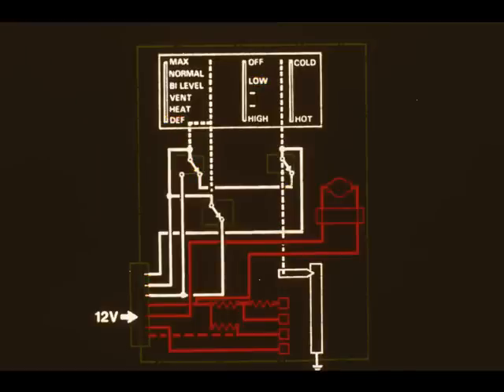The blower motor and speed control can each be tested using a 12-volt supply. Connect it to pin 5 of the 7-way socket. The motor speed should increase as successive selections are made. The highest fan speed can only be obtained by earthing terminal 4. If the compressor-mounted fuse has blown, showing that the superheat switch at the compressor has been closed, then thoroughly examine the refrigeration system before continuing with the electrical tests. The gas system should only be checked by a competent member of the staff.